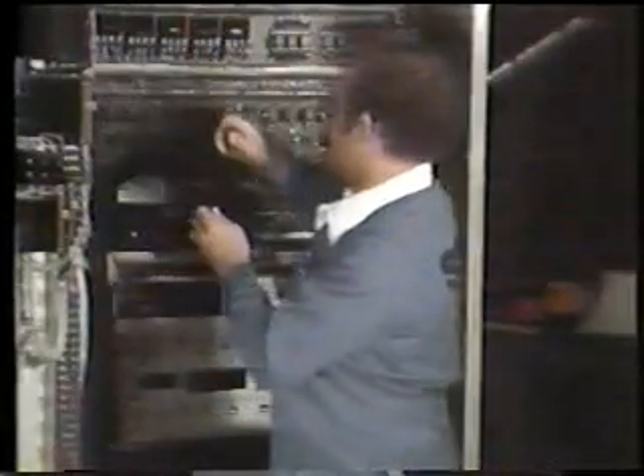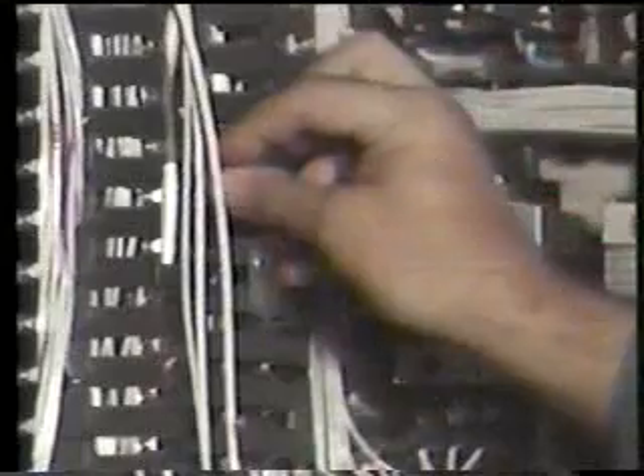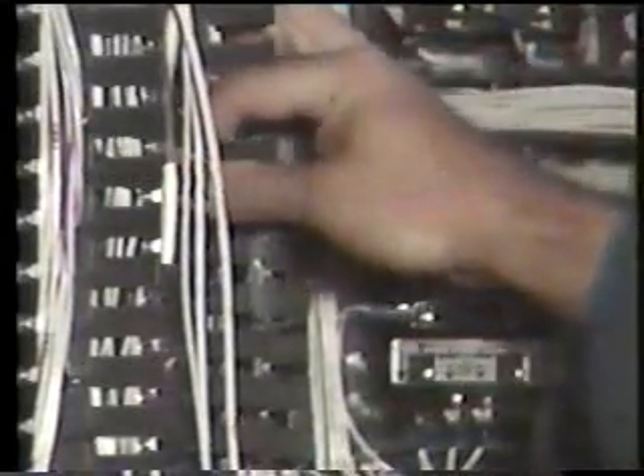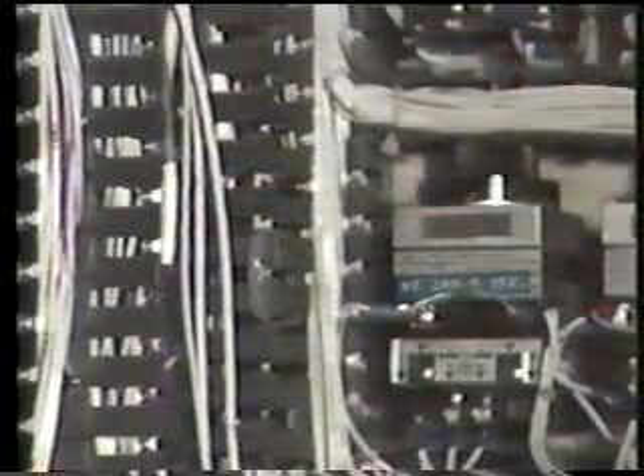Now reconnect the magnetic pickup output wire to the terminal's contact. When the package is started, verify the voltage output of the magnetic pickup. Procedures for verifying the voltage output are covered in Job Program 4 of this videotape.